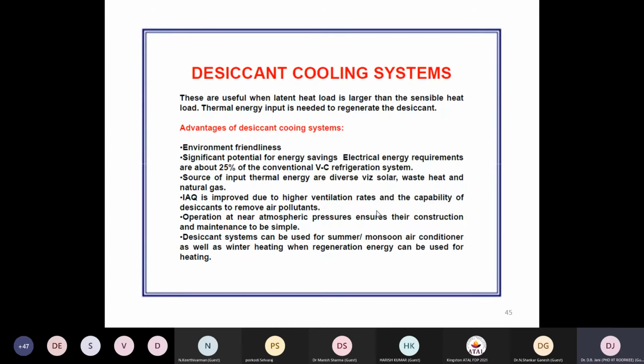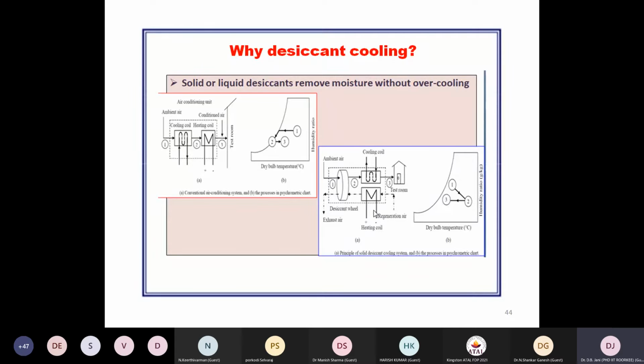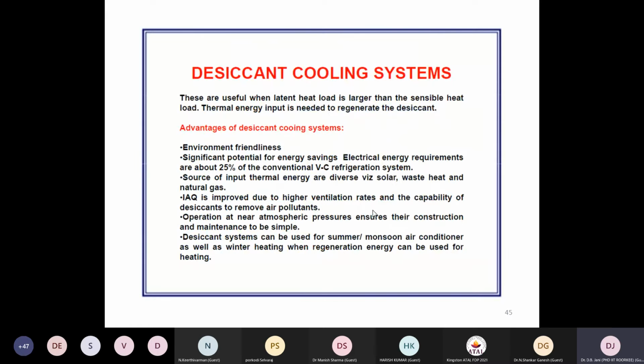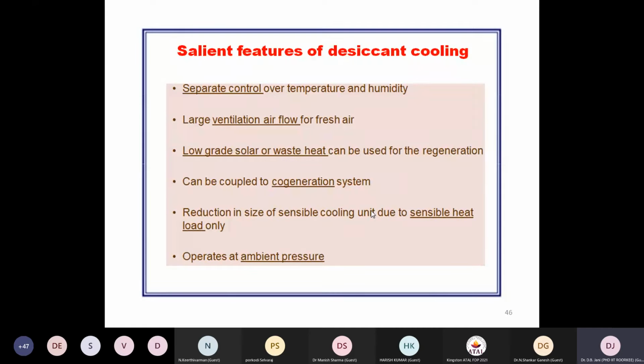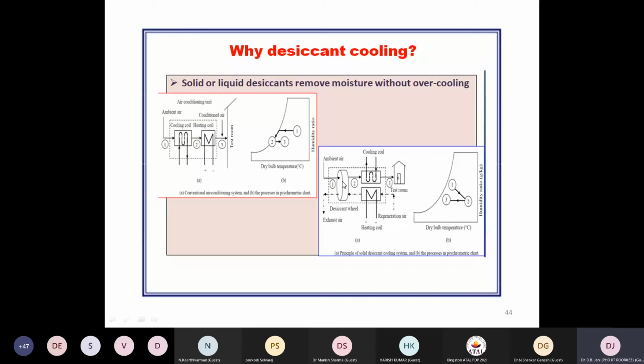HVAC. A desiccant system can be used as an alternate system by altering the configuration of the process as well as the regeneration air by altering its flow, so it can be used for summer or winter depending upon its configuration. So desiccant cooling allows separate control of temperature and humidity. Humidity is controlled only by the dehumidifier, while the temperature is maintained separately by the cooling coil. So both are separate. If the temperature is satisfied, put off your cooling coil according to the thermostat signal to the system. If the dehumidifier operation is put off according to the humidity range achieved in the supply air, make use of a thermo humidistat to close the wheel. So alternately, ambient air passed through the dehumidifier and cooling coil can be controlled in operation by the requirement.